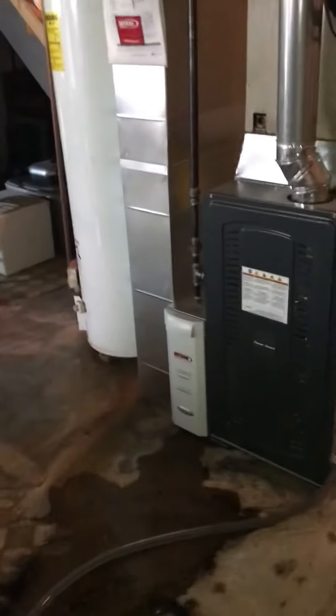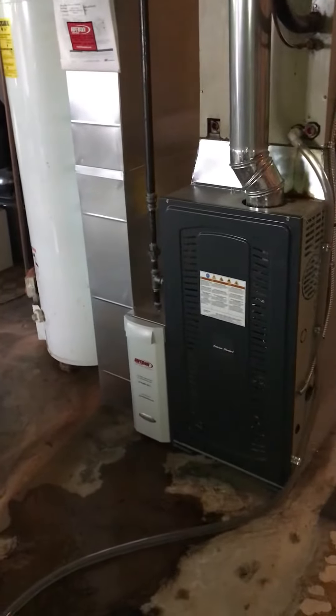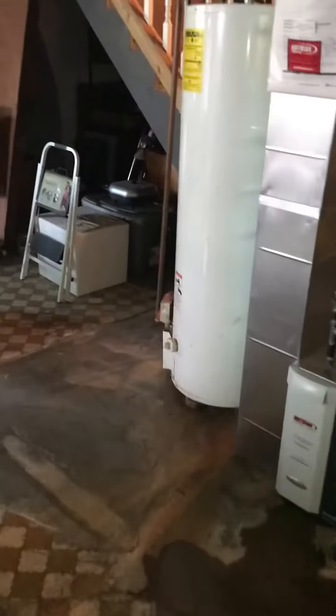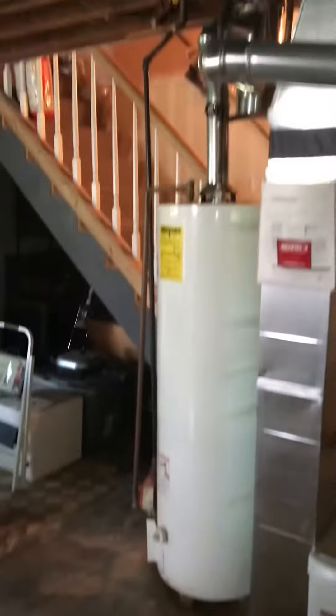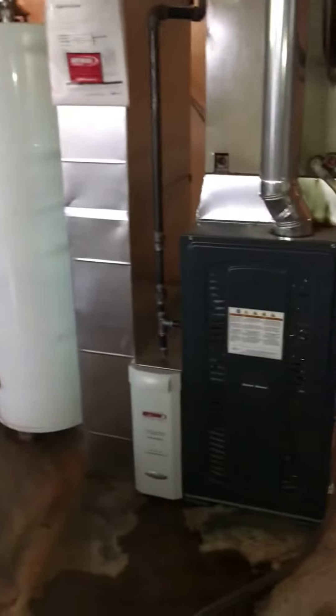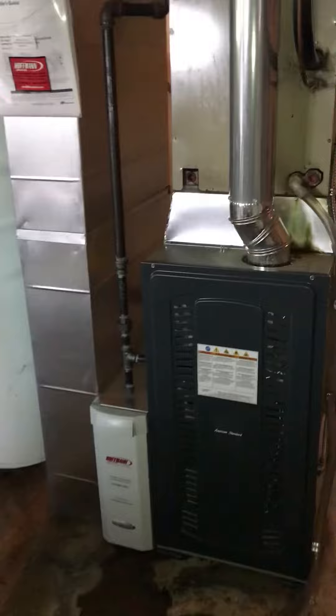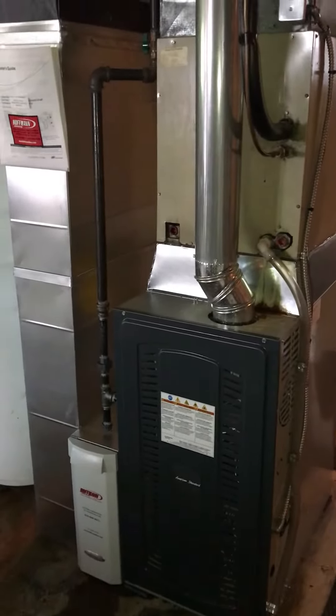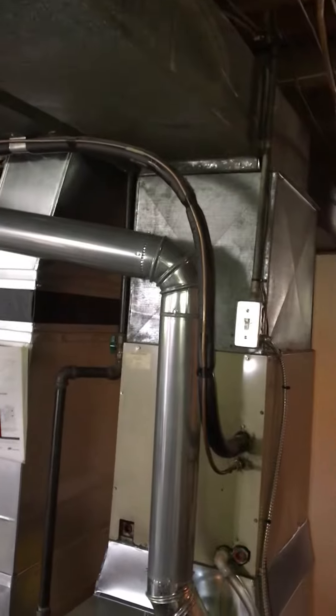We're looking at AC coil replacement. We put in a new furnace in October 2019, got all the return drop, media filter and piping tidied up. It's a B-width furnace and we have 43 inches in height from the top of the furnace to get underneath that supply trunk.